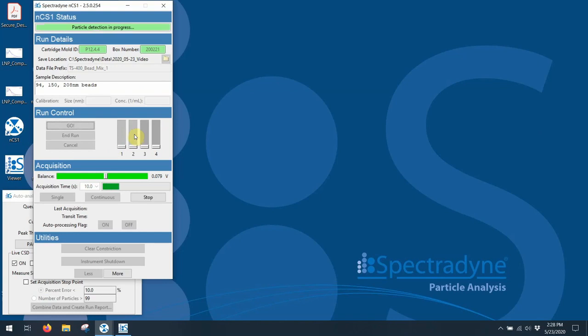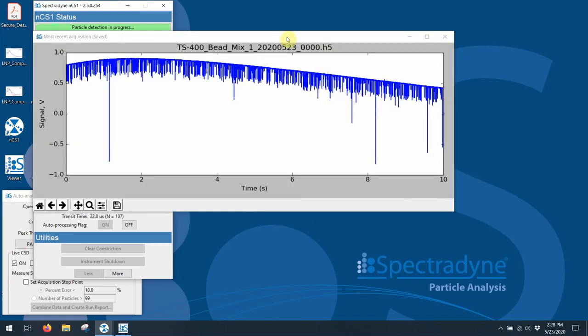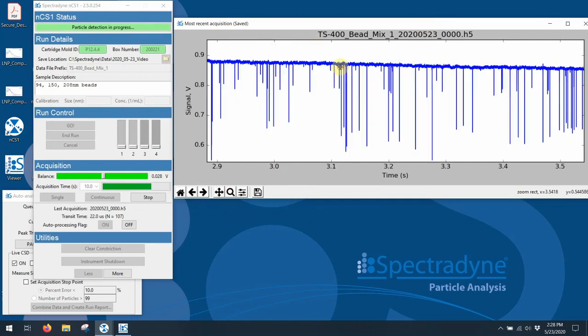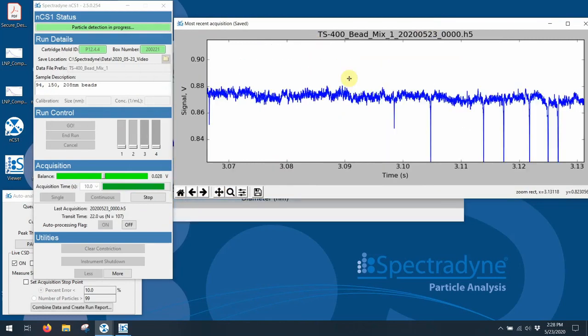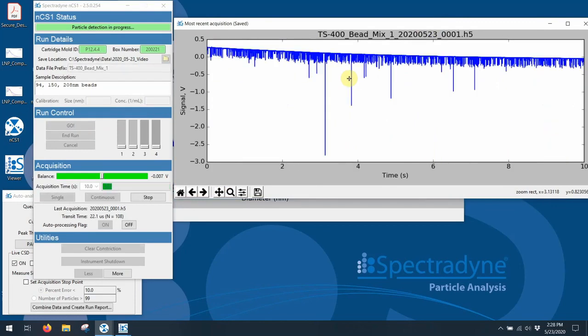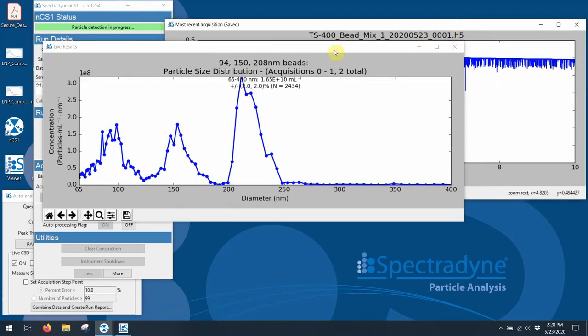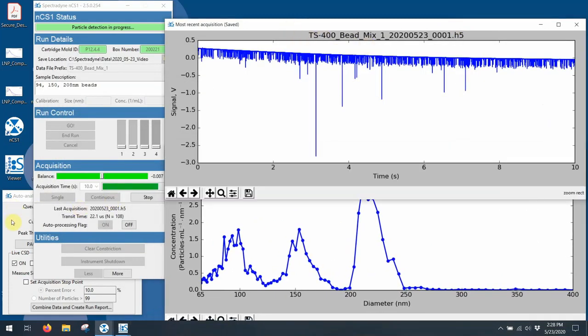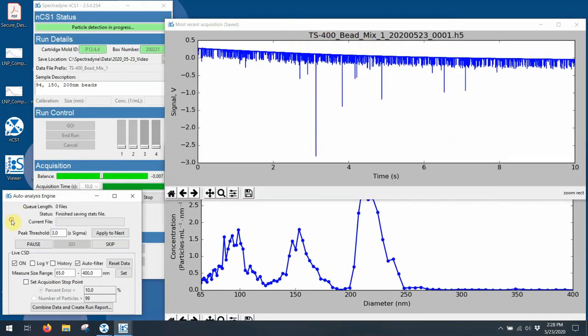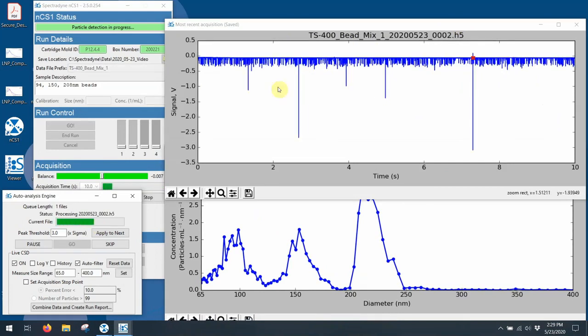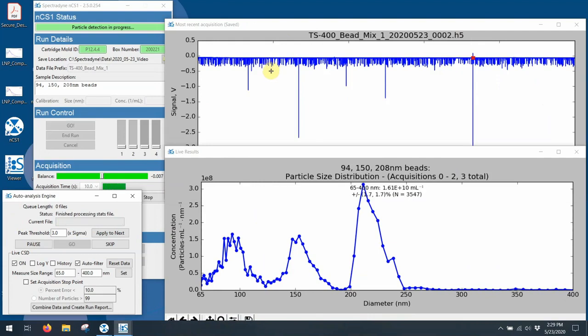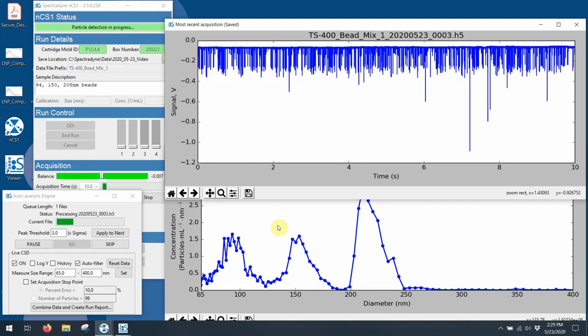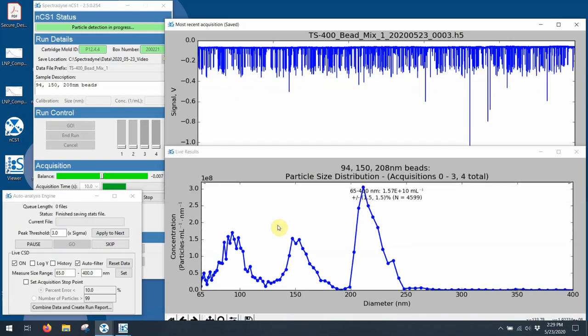So now we're beginning the acquisition. You can see the fill monitors have turned off. And we're beginning a 10-second acquisition of raw data. And here's what that 10 seconds looks like. I can zoom in on that a little bit so you can see a little closer what's going on here. Each downward spike represents a single particle transit. So what we're doing is we're taking 10 seconds at a time. And when the data is good in that 10 seconds, it gets passed over here to what's called the autoanalysis engine, where we turn these downward electrical spikes into an actual particle size distribution. And essentially what we're doing is we're converting the size of that spike through the calibration into a particle size. And then we're also plotting it against concentration.